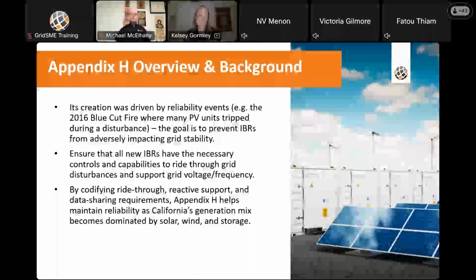So why was Appendix H created in the first place? Well, it was actually the result of some very specific events. The 2016 Blue Cut fire disturbance occurred when there were many PV units that were tripped offline. And the goal, again, of Appendix H is to prevent IBRs from adversely impacting grid reliability.